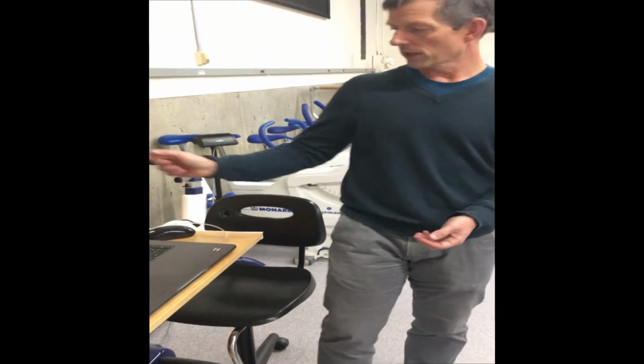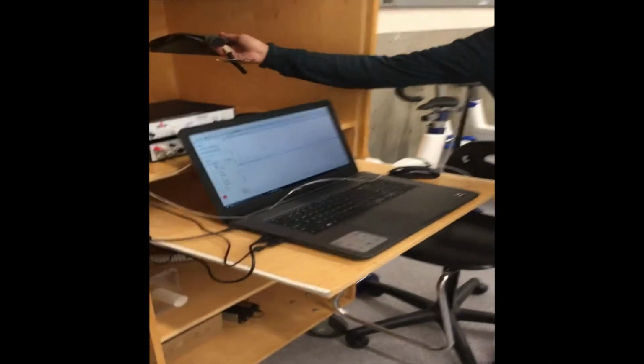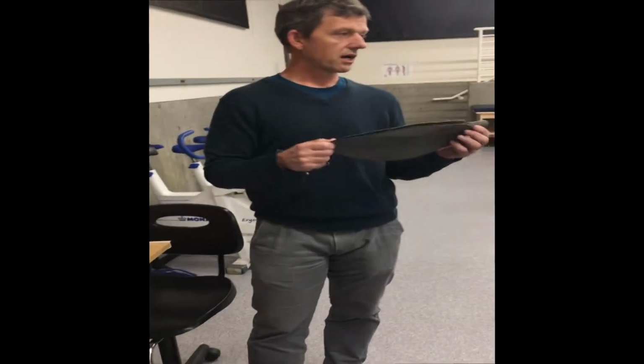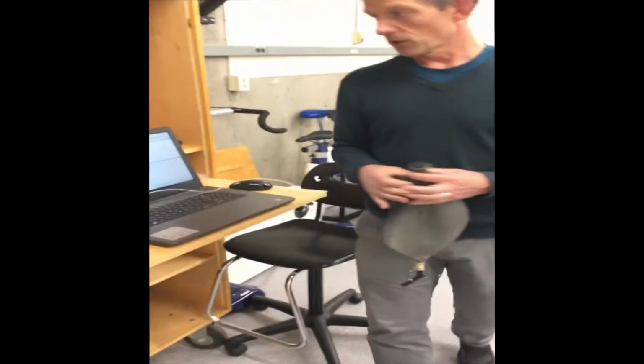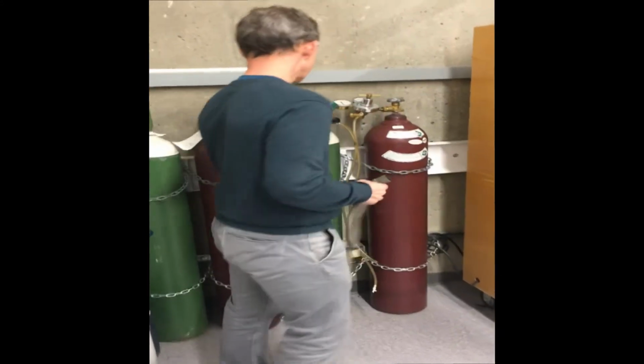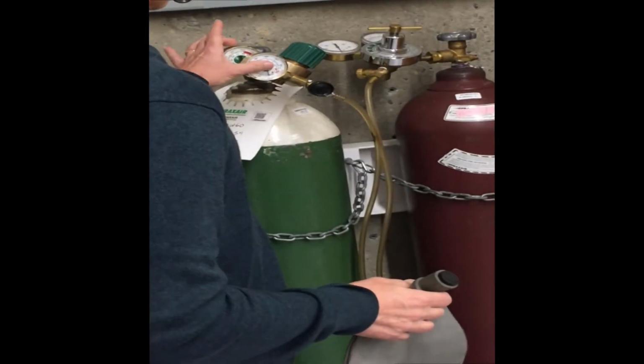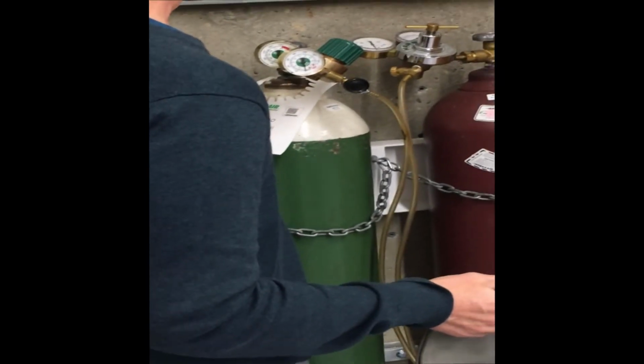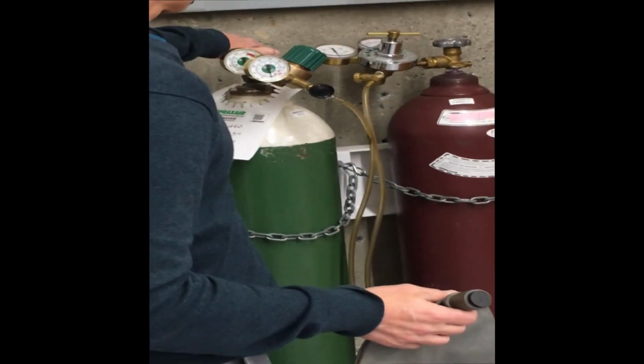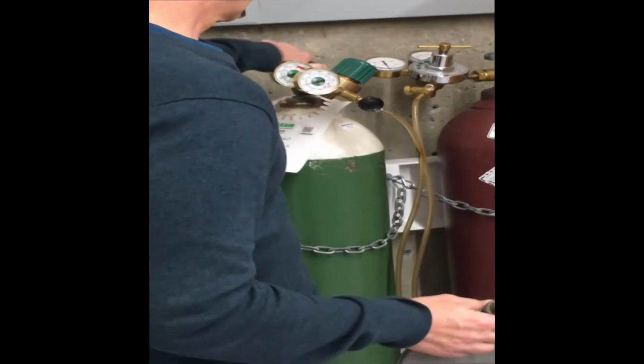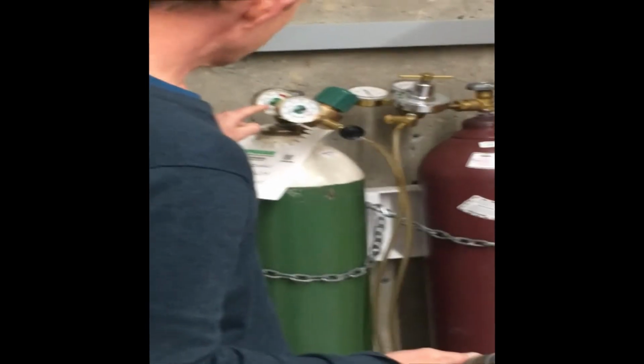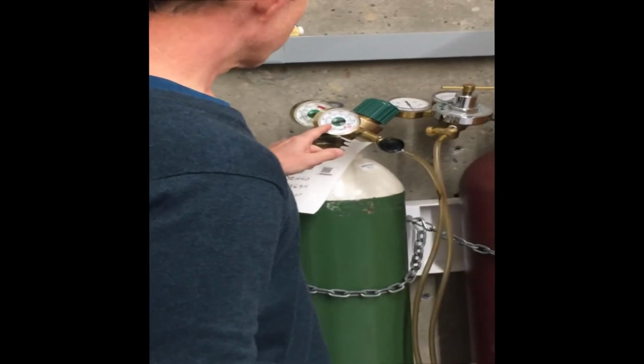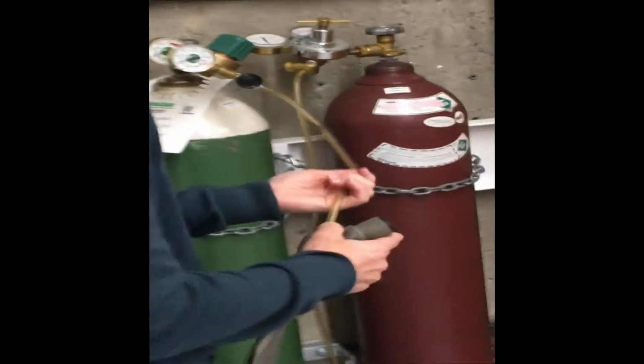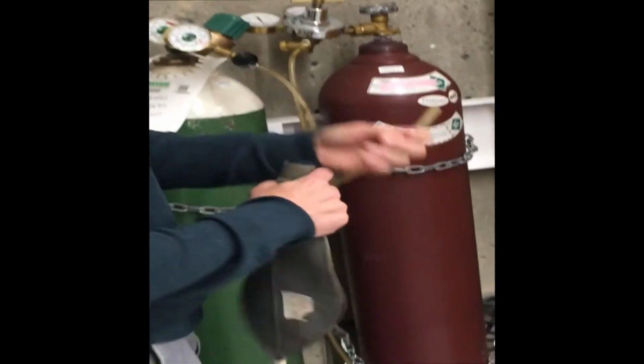So the last thing I want to go over with you is how we're going to fill up this bladder to get 100% oxygen inside this bladder. So if we go over here, we have a cylinder with 100% oxygen in. So it works under the same principle. Unfortunately, it's a slightly different regulator, but it works under the same principle. So the first thing I'm going to do is I'm going to open up the cylinder. And now I can see this is the incoming pressure. Right now it's at about 1,300 pounds per square inch. But the outgoing pressure is only around 60 pounds per square inch. So I've opened this up, I've pressurized this.